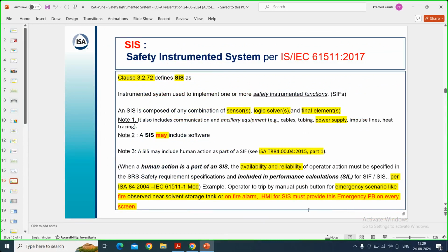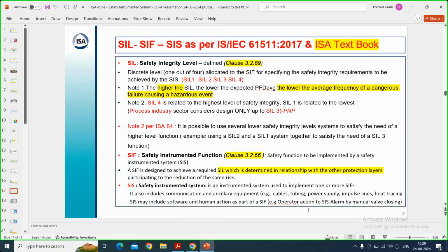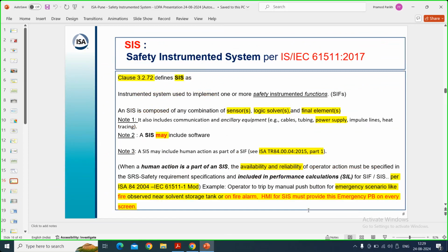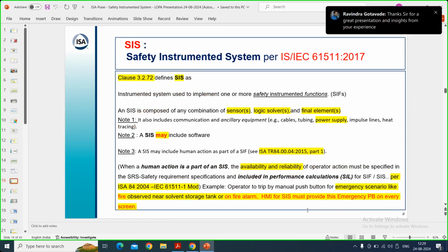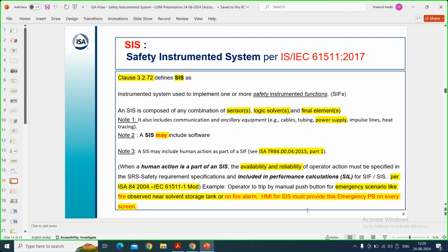Hello, sir. Yes. How is the safety instrumented system applied in medical instrumentation? In medical instrumentation, there are probably separate norms. These standards are silent on medical instrumentation applications, but when you select a sensor for medical instrumentation, you go for the specifications of the sensor and ask the manufacturer for the failure rate. If the manufacturer gives you the failure rate of the sensor, you will be able to judge whether the system will fulfill the requirement of medical science or not. But as of date, there may be a separate standard for medical instrumentation. The SIS cannot be applied for medical instrumentation.